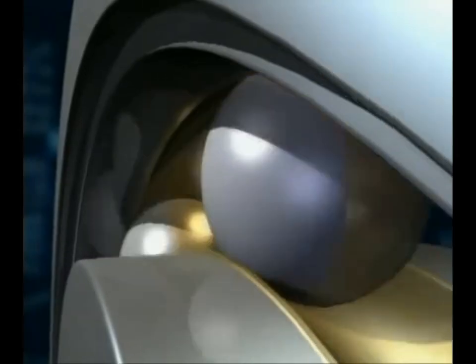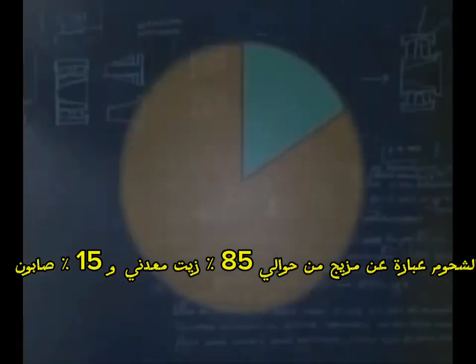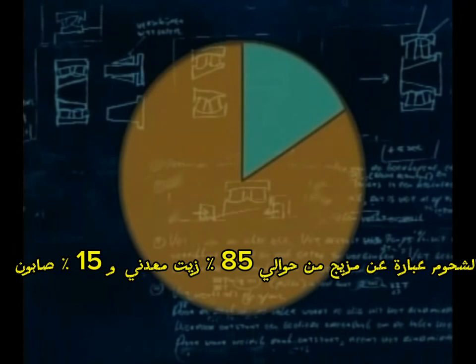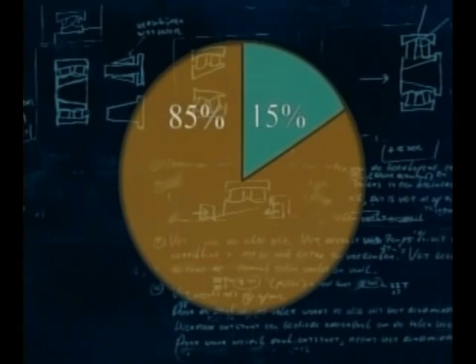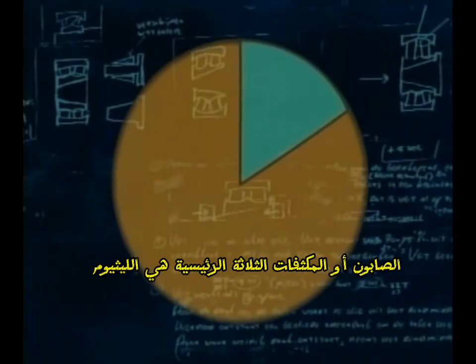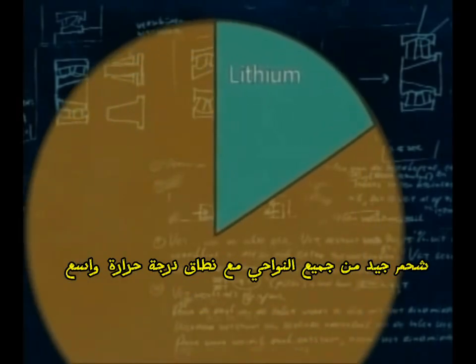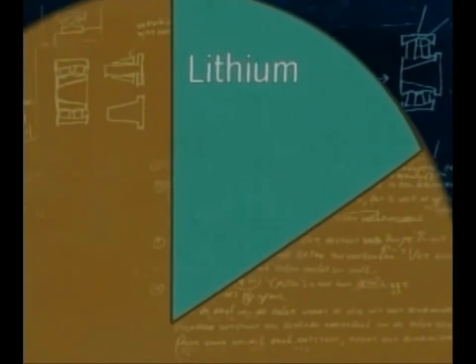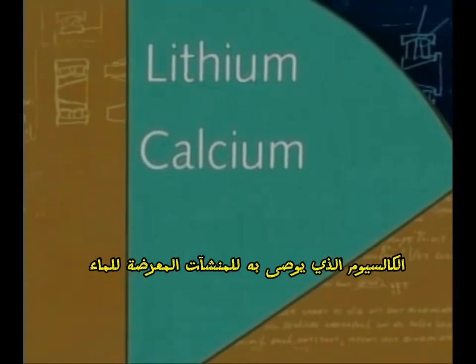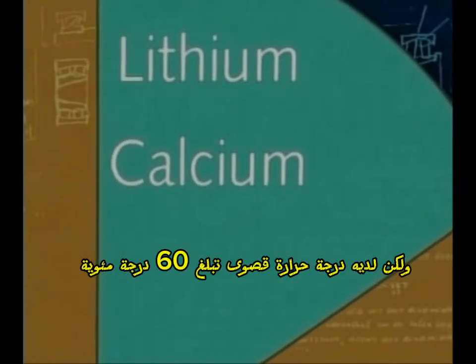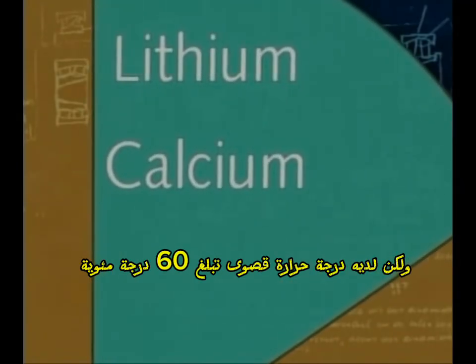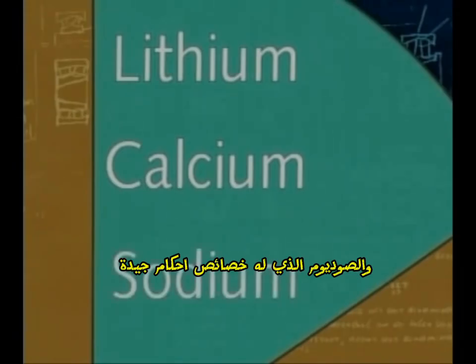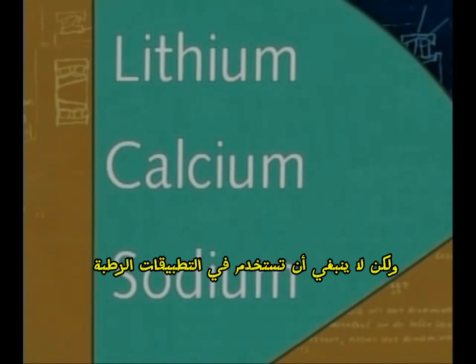Grease is a combination of approximately 85% mineral oil and 15% soap or thickener. The 3 main soaps or thickeners are lithium, a good all-round grease with a wide temperature range; calcium, which is recommended for installations exposed to water but has a 60 degrees centigrade maximum temperature; and sodium, which has good sealing properties but should not be used in wet applications.